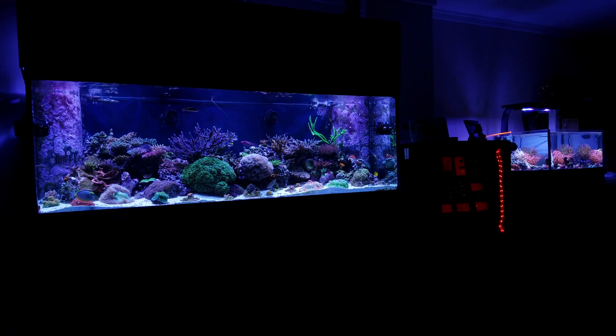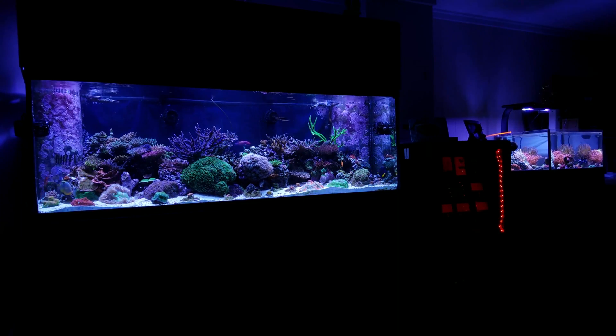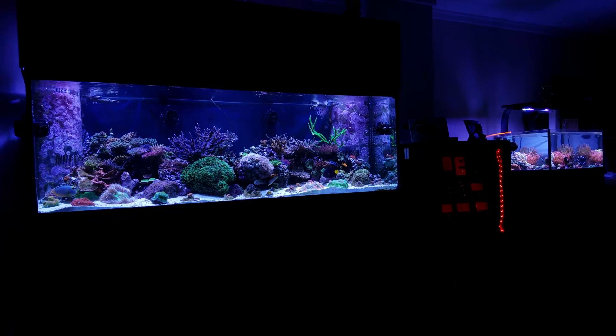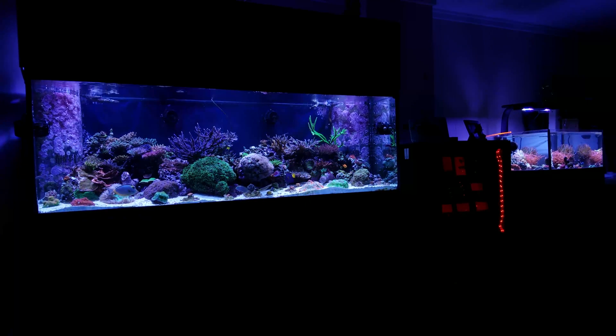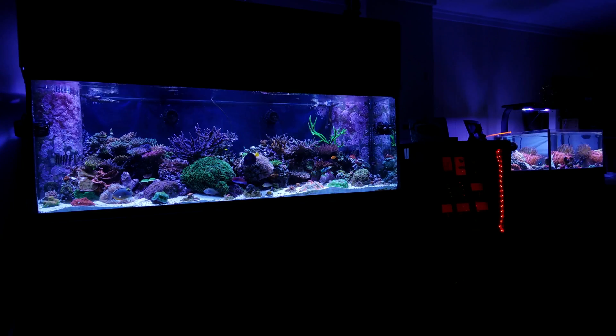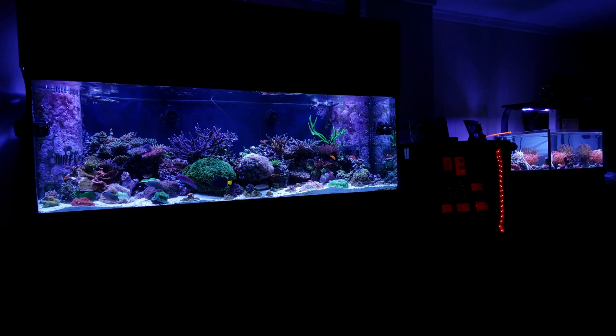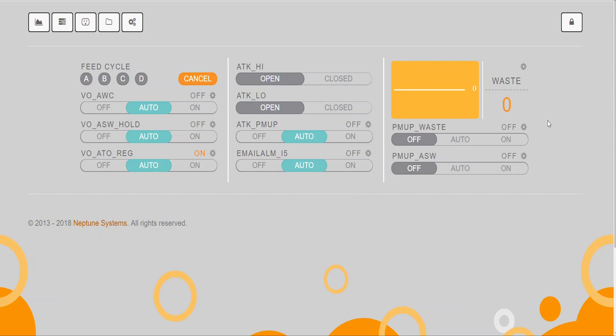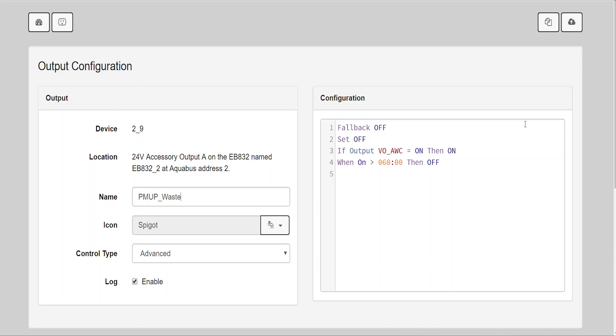Now, of course, to make all this work, we have to have some real outlets. These are outlets that are actual electrical outlets on my EB-8s, EB-832s, and my other power strips. So, pump waste, PMUP_waste. This is a pump that will send water from my sump up to my ceiling, across my ceiling, through the wall, and down into a drain in my laundry room. This is how I'm pumping the water out of my system. So the code is fallback off, set off. If output VO_AWC equals on, then on. And when on, and then this is one of those settings where you can change the times depending on how long or how short you want your water change to be. Since I want this water change to go an hour, I'm going to say when on is greater than 60 minutes, then off.